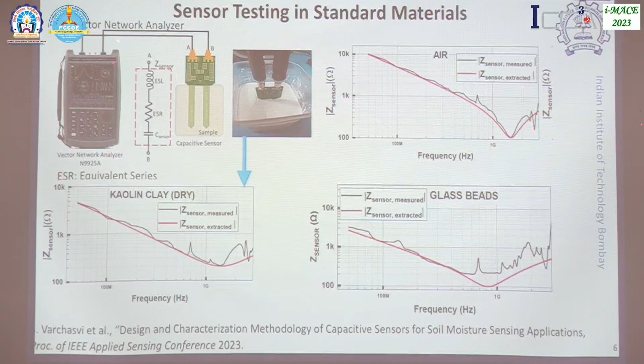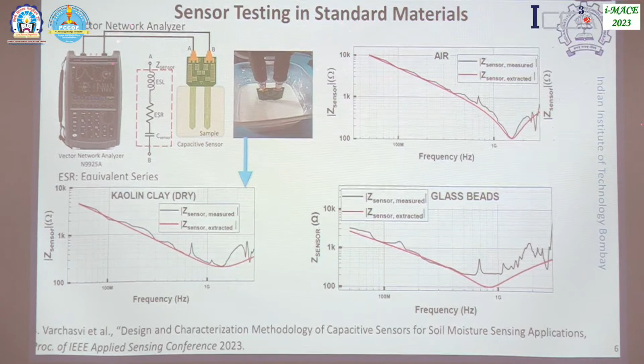This is, for example, one model, N9925A. Now here you see 3 materials. First, of course, is air. Everything starts with air. You see the black is measured and the red is the fitted, from which we eventually extracted these 3 parameters of the model. Naturally, measurement will show some fluctuations with frequency. Even if you repeat the measurement, you may get a little different result. But if you look at the average or envelope of this plot, the red color still shows the behavior of this model compared to reality relatively well, except for glass beads, which is still okay because this is at the resonance frequency and we want to operate well below the resonance frequency. Therefore, we have to choose frequencies around, say, 100 to 200 megahertz so that we would be able to get it right for all kinds of materials, at least standard materials.